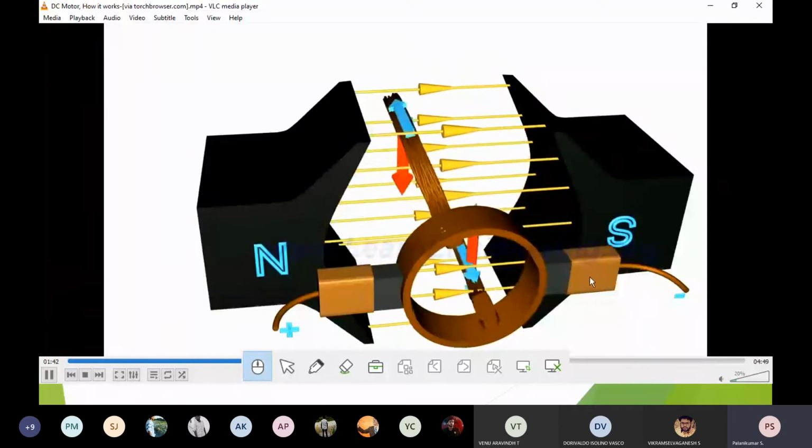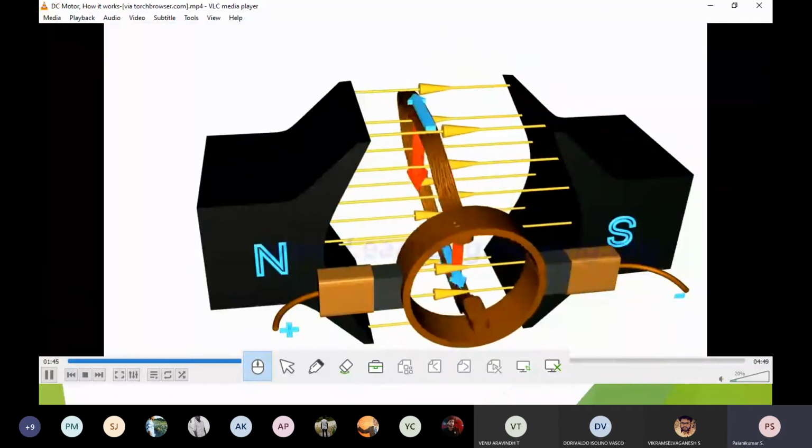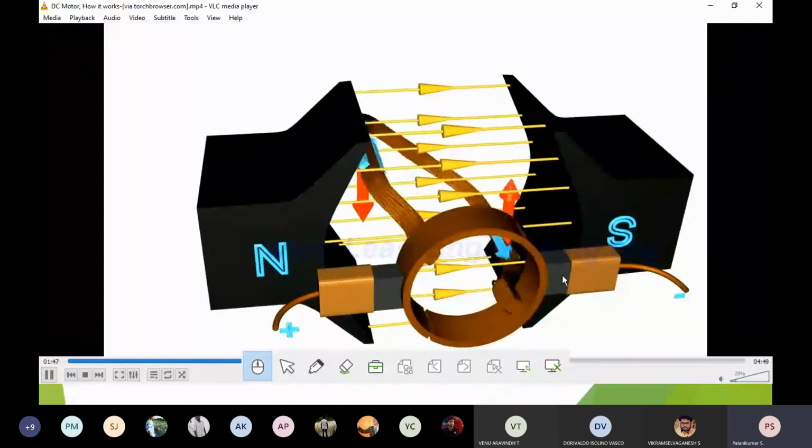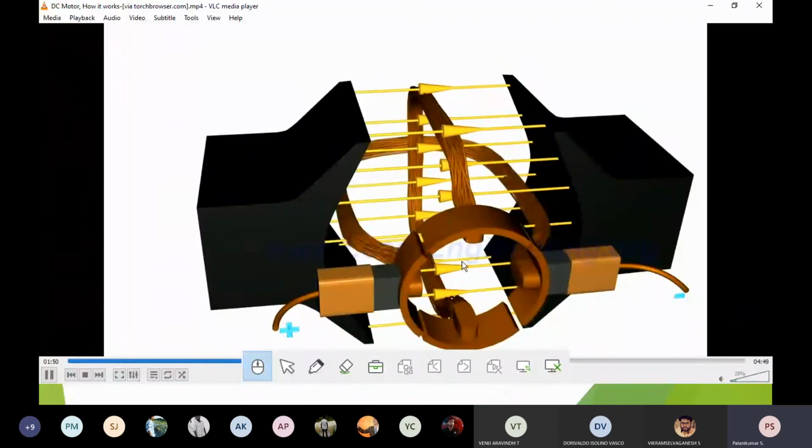So how are we ensuring this? A sliding contact by the carbon brushes over that. In order to always keep contact with the circumference of the commutator, at the backside of the carbon brush one small spring will be there. Through that spring, the carbon brushes are held. Carbon is a very good conductor. Apart from that, even though it is carbon, it has very high strength. I think the manufacturing of carbon brushes is a separate engineering field alone.